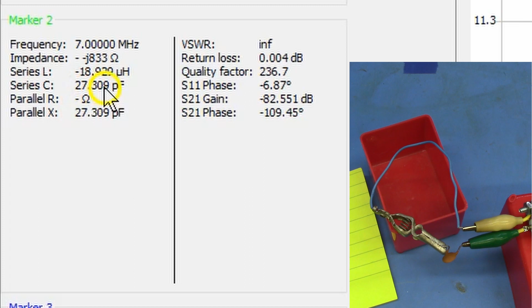But just to double check ourselves, we're going to disconnect our fancy standard here and put in our known 27 picofarad high precision NPO capacitor, do another scan, and it tells us we have 27.309 picofarads. That's really good, so this calibration looks really good.